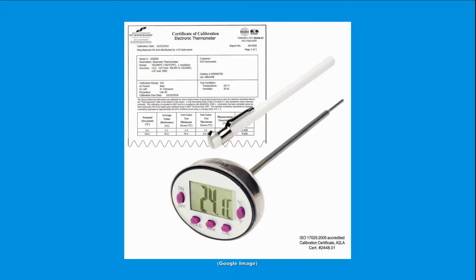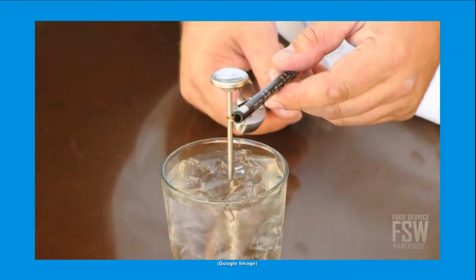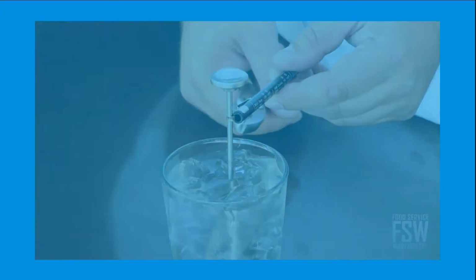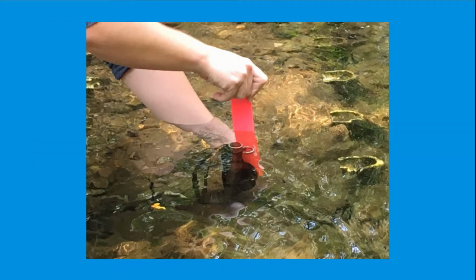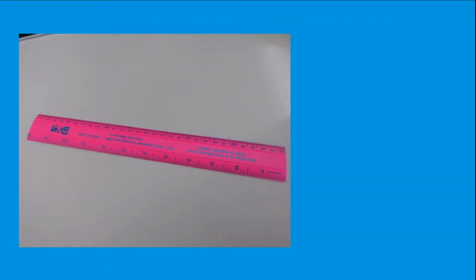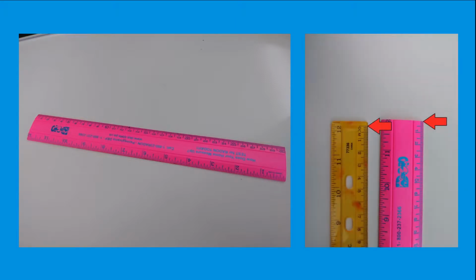For performing quality control on water temperature, Stroud uses a Durac waterproof electronic thermometer. This instrument is factory calibrated. It only needs recalibration every 6 months or so. The suggested process for this specific instrument is the freezing point method. For performing quality control on water depth, Stroud uses a simple ruler rather than an electronic instrument. No calibration is required for this tool. Do take note of where 0 is marked on the ruler since that designates where the front of the ruler is placed when QCing water depth.